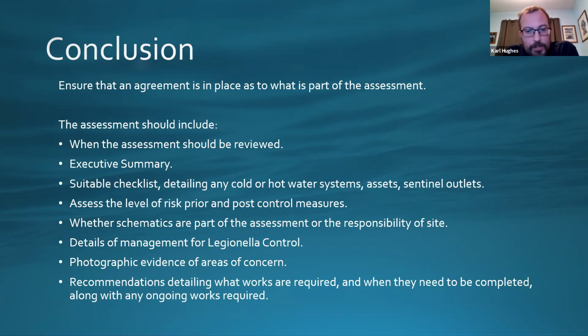Photographic evidence of areas of concern, for example a dead leg located in the roof space next to a cold water storage tank. Details of the management for Legionella control - you nominate responsible people, your deputies and your duty holder. And any recommendations detailing what work is required, whether ongoing or remedial works. If it's remedial works, how quickly you need to get that done - for example removing dead legs or that cold water storage tank, you'd put those down as immediate risks. Some of the others will take a little longer to get rid of.